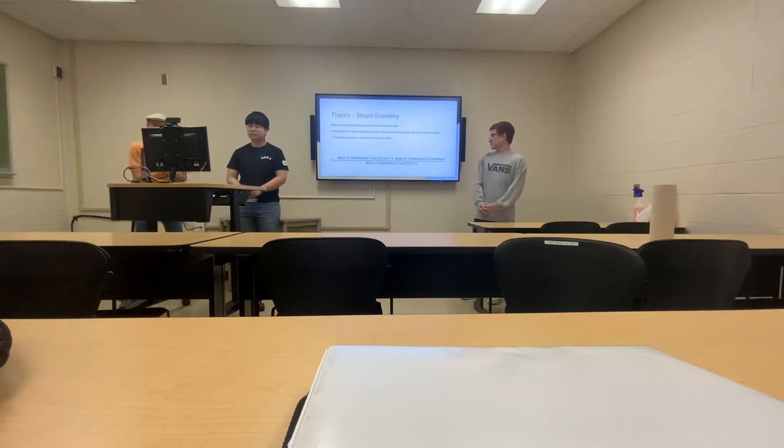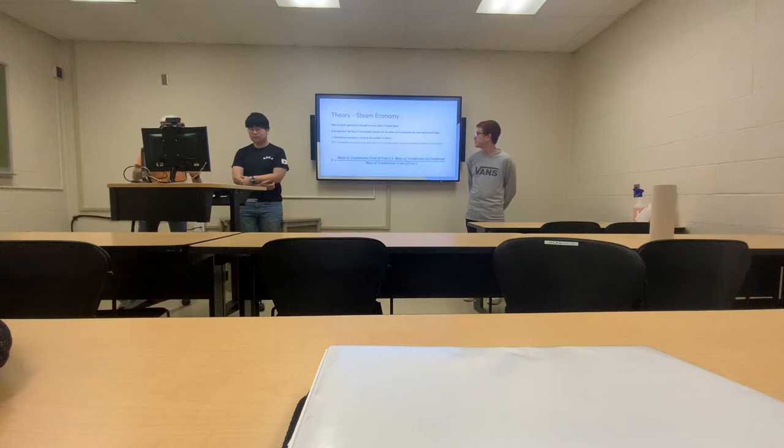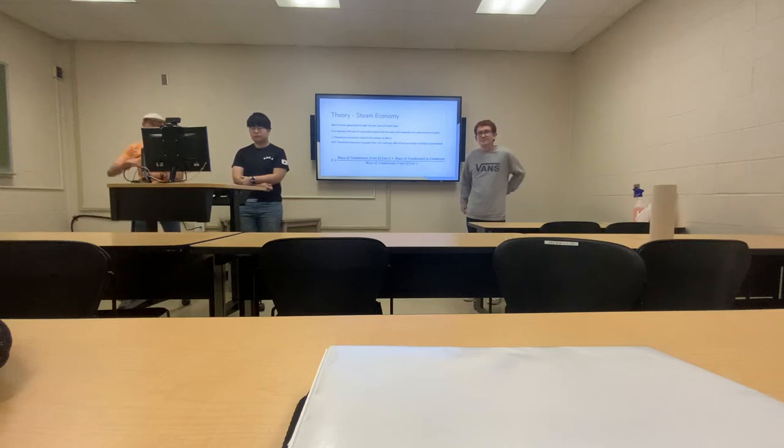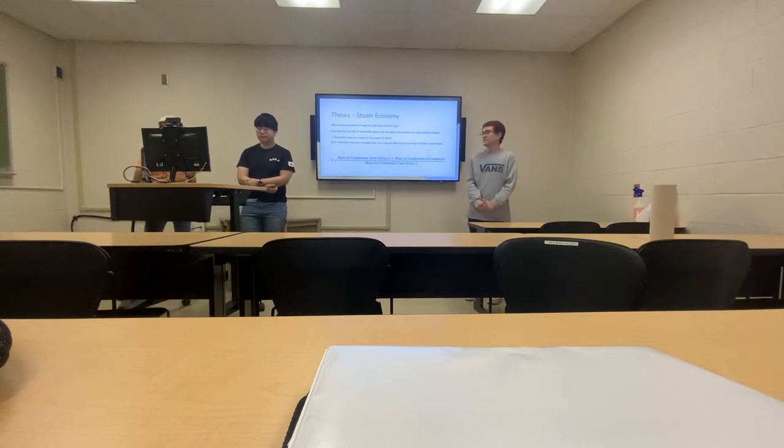Dr. Essen earlier told us that the theoretical maximum steam economy you can have is 1:1. That's actually not true, it's higher, because you don't have to have the same pressure, and the steam going in could actually be superheated. So there's a lot of variability here. If you had two effects, or even just one effect, and you condense superheated steam at atmospheric pressure, you're going to get considerably more steam than the single pound of steam, because you're ignoring the amount of energy that was originally in the system. Or if you dropped the vacuum as you went to another effect, you could boil off more just because the boiling point is lower. So there's a little bit of play going on in there.